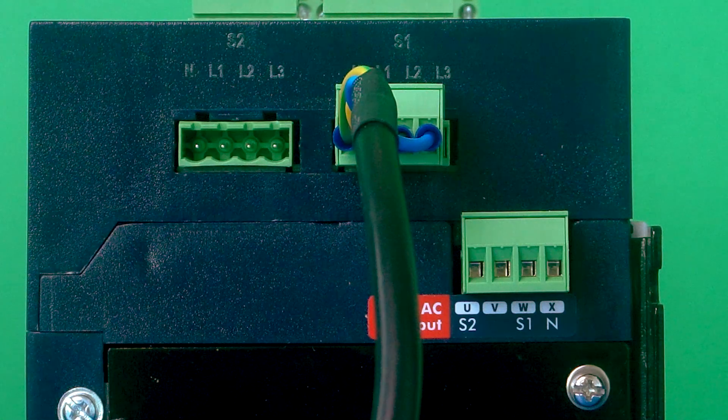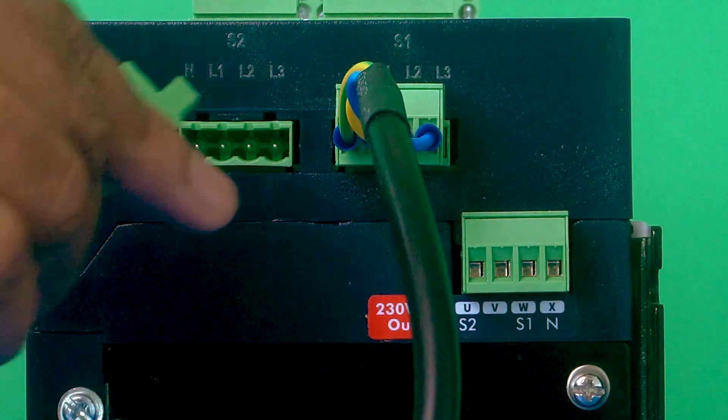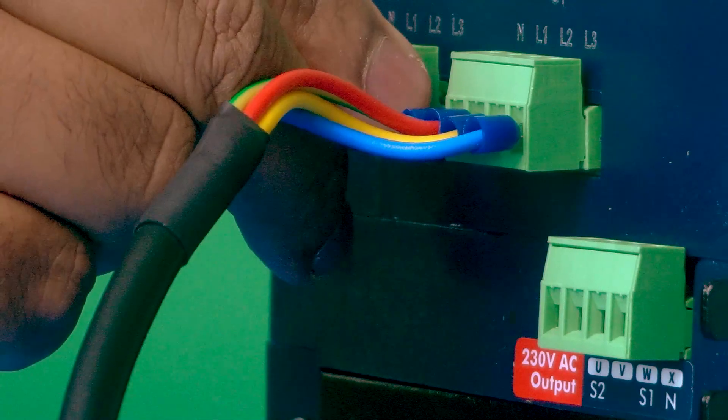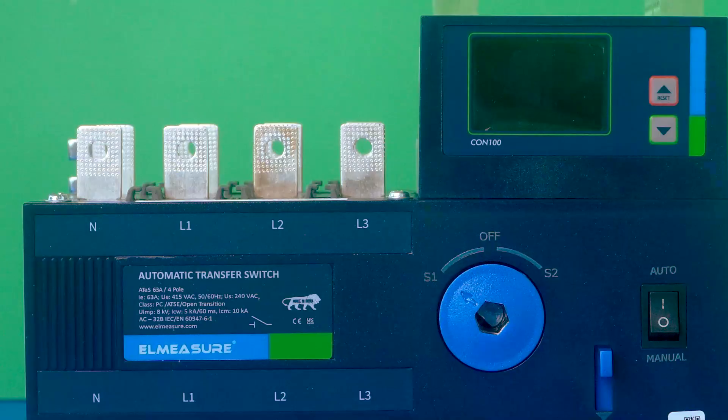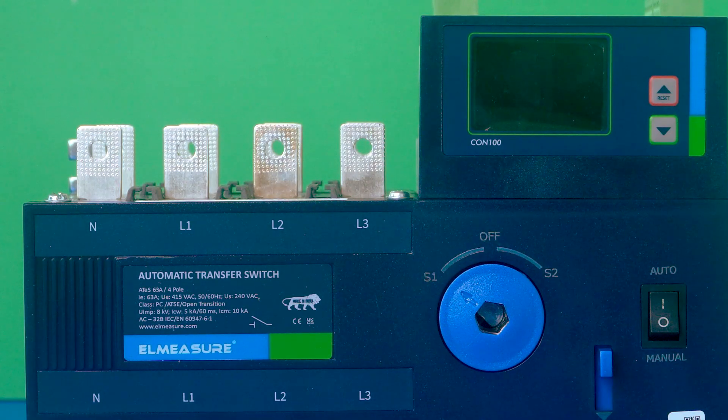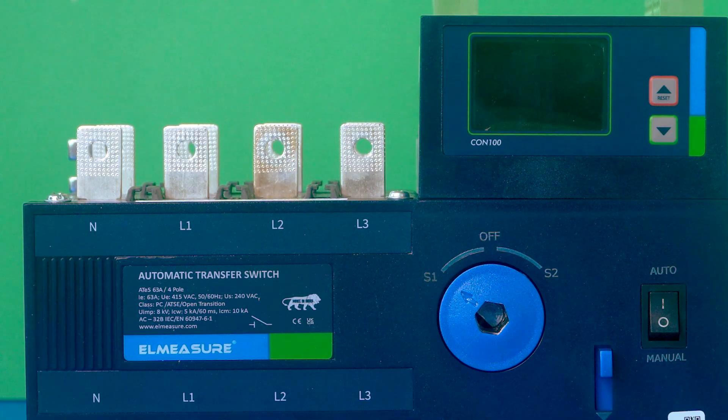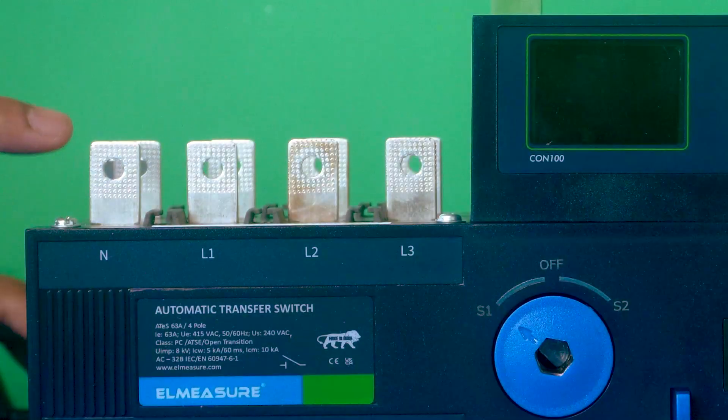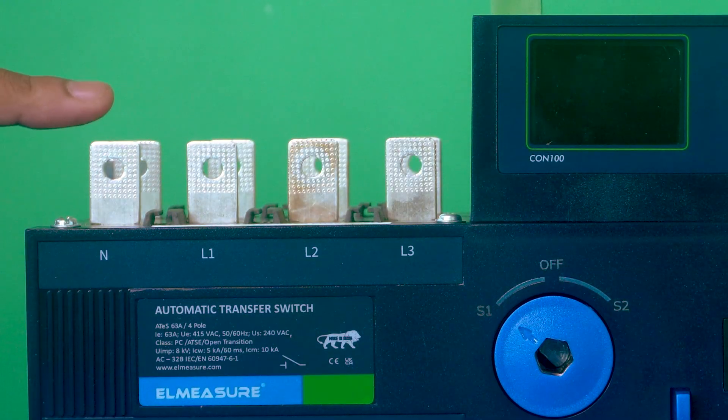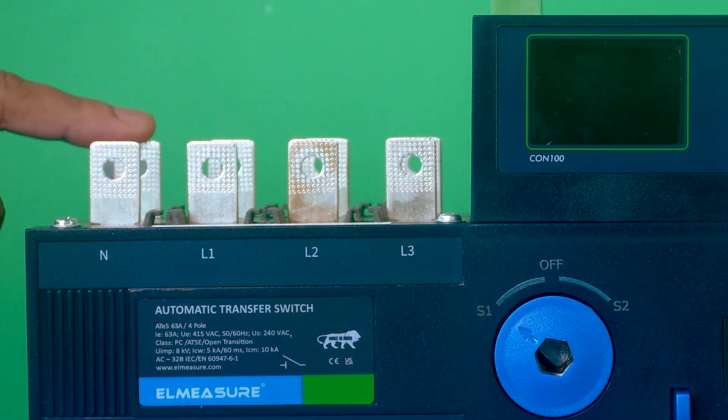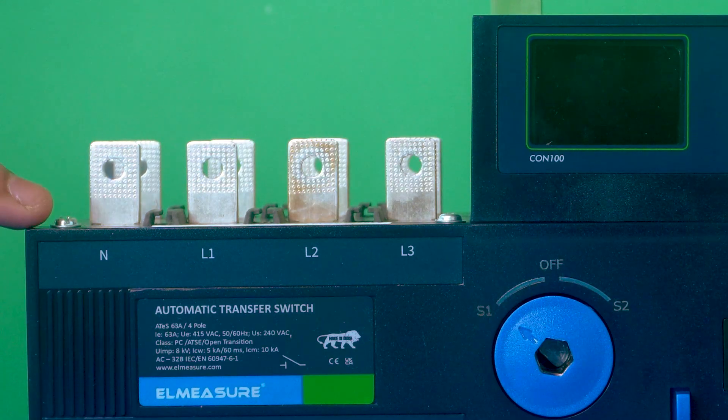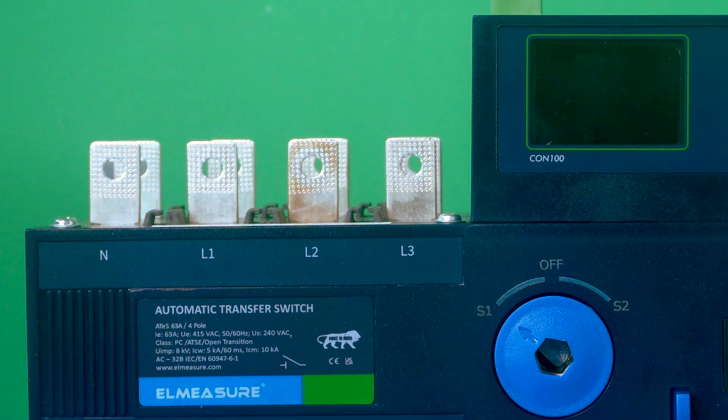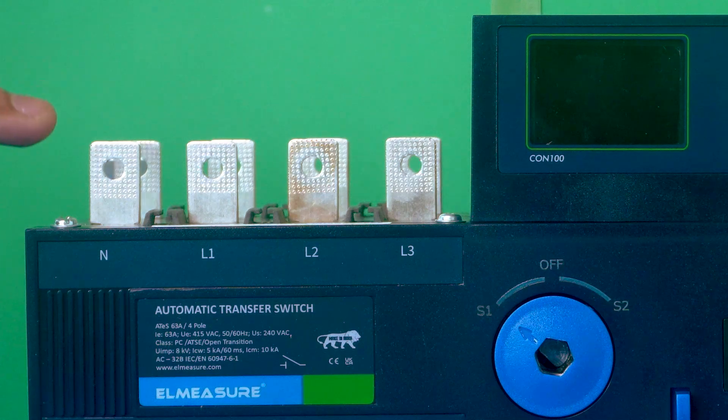We have already connected the wiring harness to the voltage feed connector. Now we need to connect the other side of the harness to the incoming busbar or cable side. This is the incoming side of source 1 and this is source 2. The labeling has been done - neutral, L1, L2, L3 - so according to that, we need to connect the wiring harness.